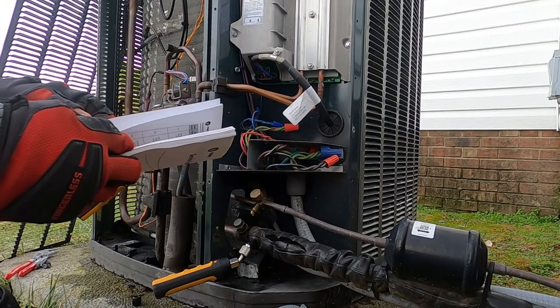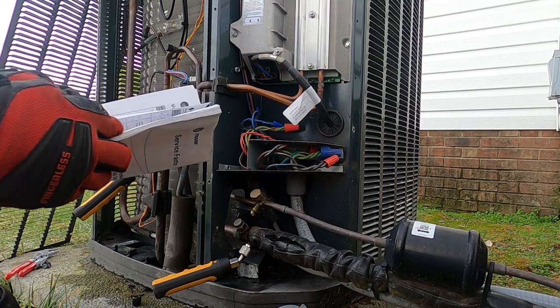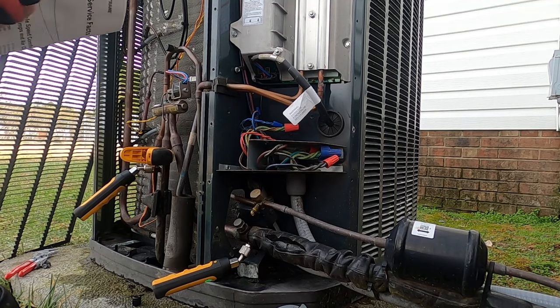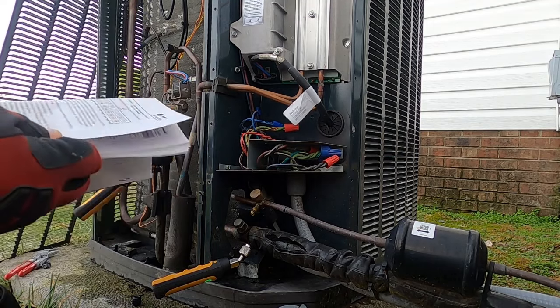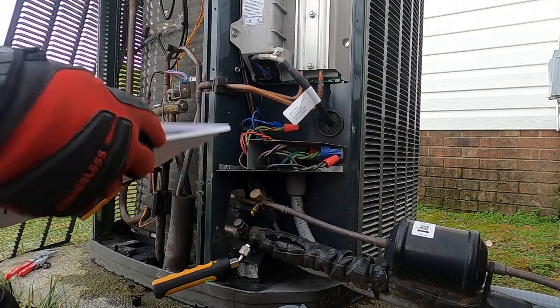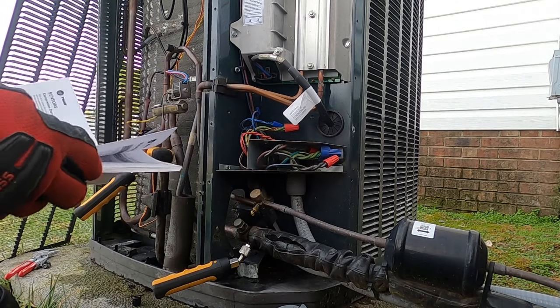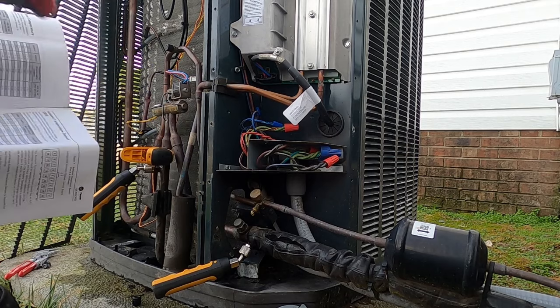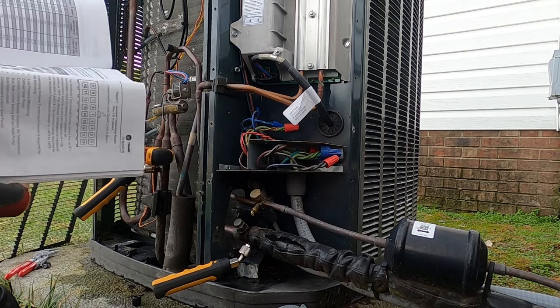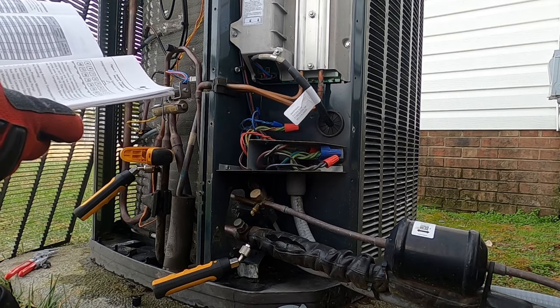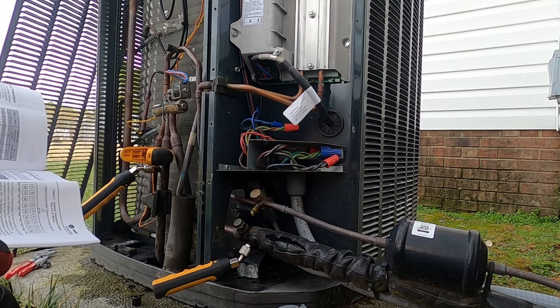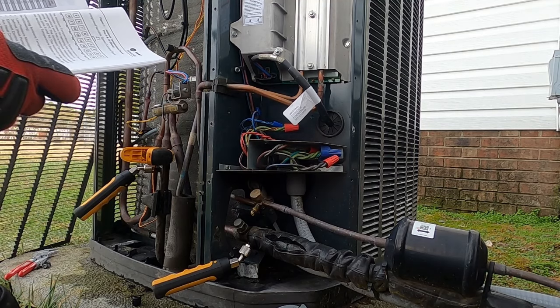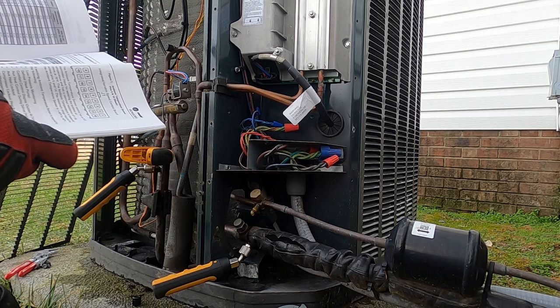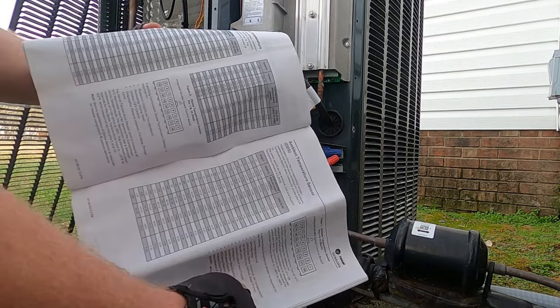Alright guys, I've got the book out, so I've already checked the temperature sensor down here on the true suction line. It had 1.08 volts DC, which is about 70 degrees. I got 70 while it was sitting here not running. It was 71 degrees on that pipe. And I'm going to see what my superheat is on this thing as it runs in heat. I'm going to check this transducer real quick. There's a chart for that in the book.